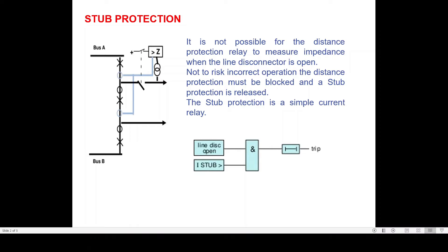But if you see, when the 89L isolator is open, that means this feeder is definitely out of service. If this feeder is not in service, why do you require any protection? The reason is that even though this feeder is not in service, if you have closed these three circuit breakers, you now have a section between these two buses. Whenever there is a fault in that section, you have to isolate this fault also, and to isolate this fault you need a protection system.